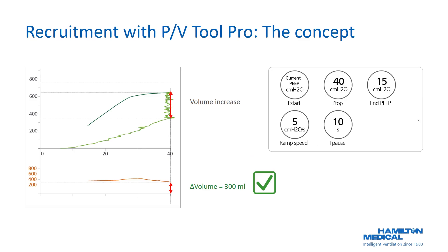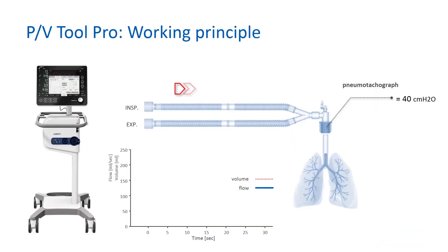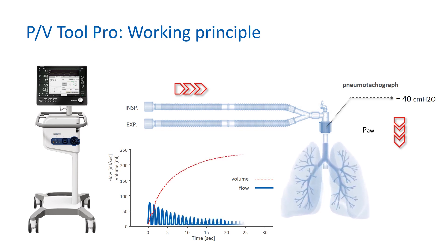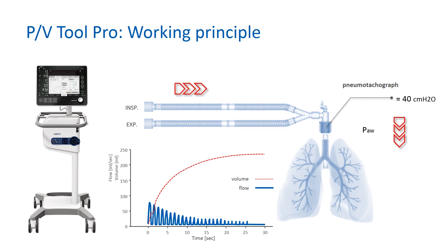With the PVTool Pro option, you have the ability to quantify the effectiveness of the recruitment maneuver by measuring the volume increase at end inspiration. During the recruitment portion, the ventilator maintains a constant pressure of 40 centimeters of water for 10 seconds. If some recruitment occurs, the total volume of aerated lung increases and, as a consequence, pressure at the proximal airway decreases. The ventilator then inflates using little spikes of flow to maintain airway pressure at 40 centimeters of water.